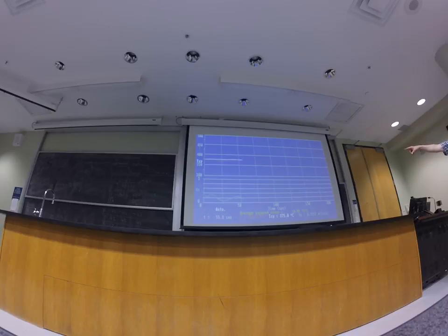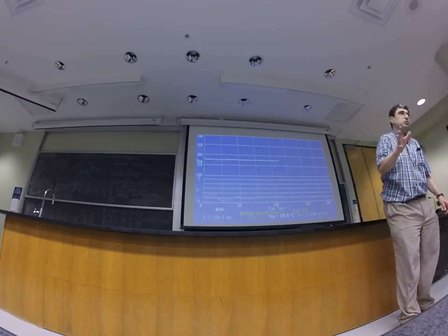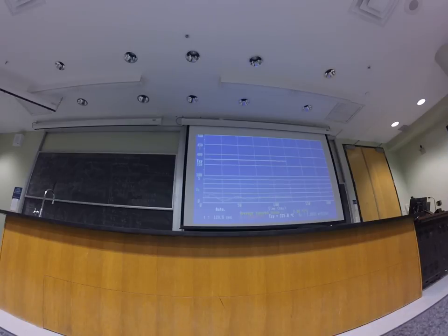Why do I have these big deviations? Because of the very bad initial tuning at the beginning. That really moved the system away. One thing you'll notice is that I have oscillations. You don't want oscillations, particularly if they're not dying out fast. This is not too bad, but it's not great. We'll take a full 15-minute break, but let's finish this. Here was a disturbance. It brings it back exactly to the set point.